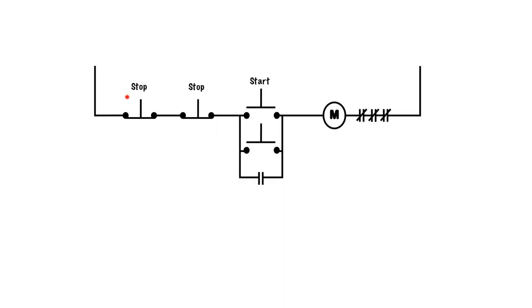Now looking at it here, we have a stop which is in series with the stop. Anytime you want a circuit to stop, the contacts need to be normally closed and they need to be in series with one another so that no matter what, it will kill the circuit or prevent power from coming across to any point.